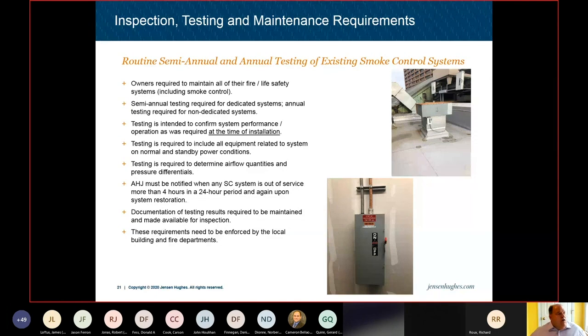So first off, any owner, basically anywhere in the U.S., is required to maintain any fire and life safety system, whether it's a fire alarm system, a sprinkler system, or smoke control system. So smoke control systems are required per code to have routine inspection, testing, and maintenance. There's a requirement to test those dedicated systems semi-annually. So dedicated systems are typically your stair pressurization systems. Annual testing is required for non-dedicated systems.